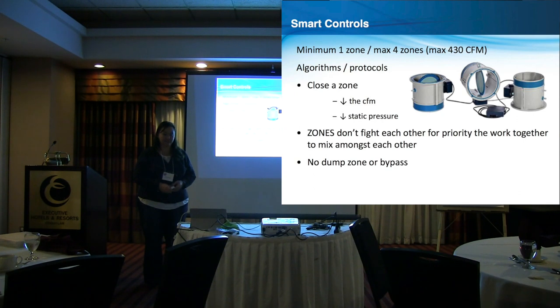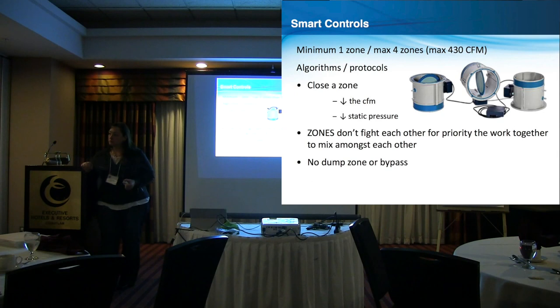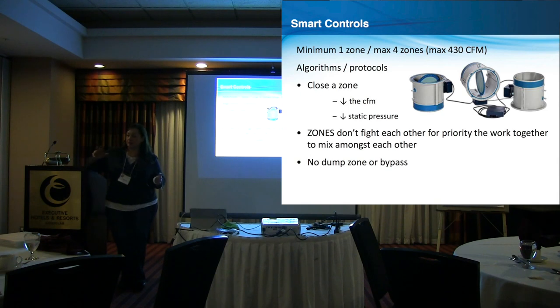Just one last question. When it is zoning and you're shutting zones down, does the modulation of the fan happen based on static pressure, or is it just the percentage of zones open? I think it's a combination of everything. The fundamental design is to keep that static pressure correct, so that's in the design off of those mains. We're keeping that 430 true for the 8-inch.